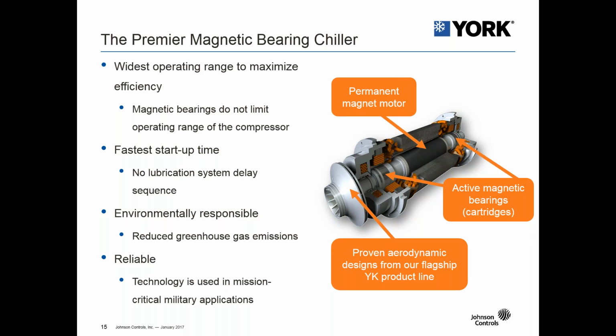But the YMC² is allowing the chiller to operate using the magnetic bearings in a very wide operating range to maximize efficiency. So the bearings do not have as much of an operational limit as you would see on a traditional system that requires system pressure differential or a pump or cooling requirements for the lubrication system. It also has very fast startup time, so if you have a critical application that needs a fast restart upon a power failure, or a process that needs to come on very quickly, there is no startup time required for the lubrication system to make sure there's adequate system pressure differential. So that eliminates a lot of time required to do a startup.